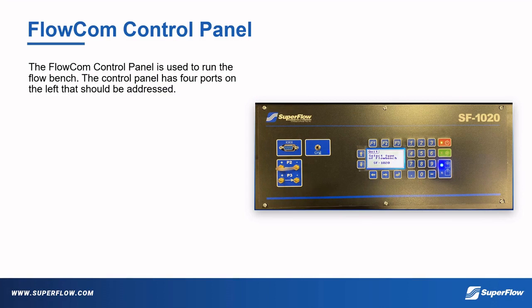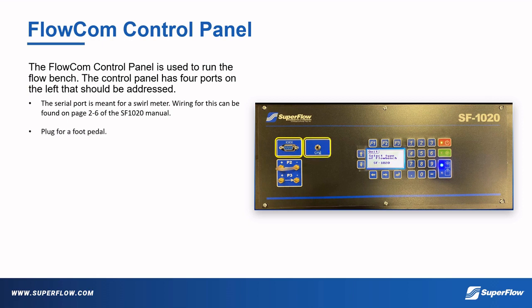Pictured right is the FlowCom control panel. This control panel has 4 ports on the left that should be addressed. The first is the serial port, which is meant for a swirl meter. Wiring for this can be found on page 2-6 of the SF-1020 manual. Next to this is a plug for a foot pedal, which the operator can use to operate the flow bench.